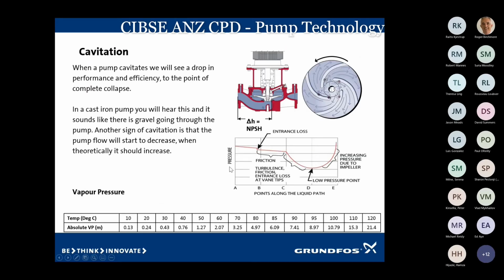So looking at cavitation and how it actually happens, as I mentioned, when the water is in the pipework and it's leading up to the intake of the pump, atmospheric pressure is pushing onto the surface, forcing the water through the non-return valve, up the pipe and into the pump. Where cavitation works is right at the intake of the pump at the impeller vanes.